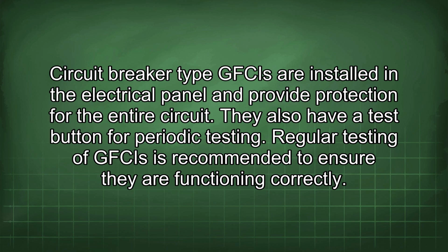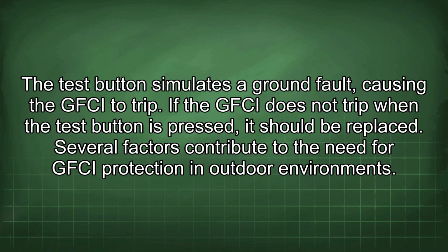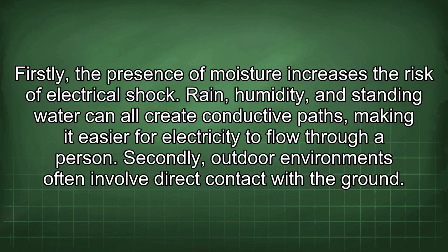Regular testing of GFCIs is recommended to ensure they are functioning correctly. The test button simulates a ground fault, causing the GFCI to trip. If the GFCI does not trip when the test button is pressed, it should be replaced. Several factors contribute to the need for GFCI protection in outdoor environments. Firstly, the presence of moisture increases the risk of electrical shock. Rain, humidity, and standing water can all create conductive paths, making it easier for electricity to flow through a person.